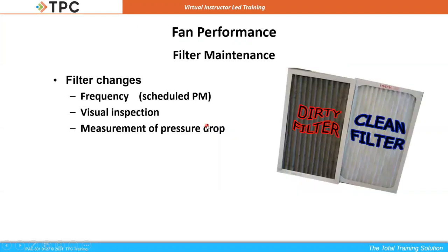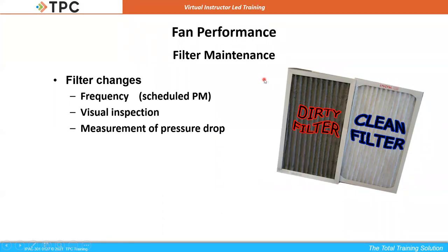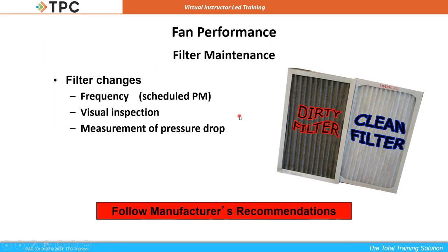Again, can't say enough about making sure that your filters are clean. Changing the filters, scheduled PM, visual inspection. So I can hold the filter up and look. If I see light through, that means that the filter is clean. If I don't see light, if light can't get through, air is not going to get through. And pressure drop, Magnehelic or manometer, they're both kind of the same terminology.